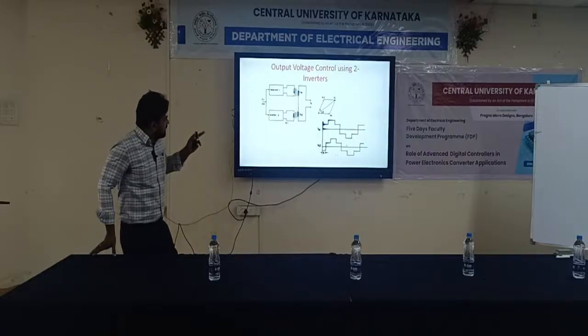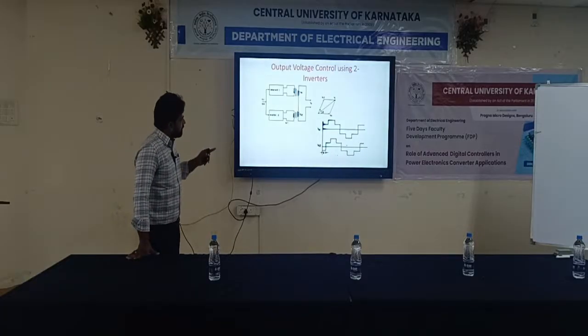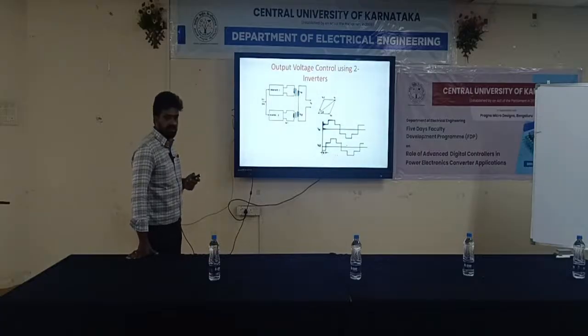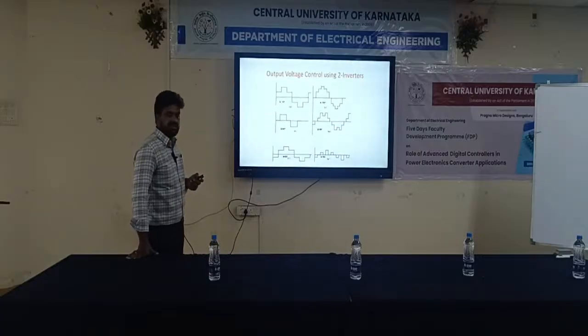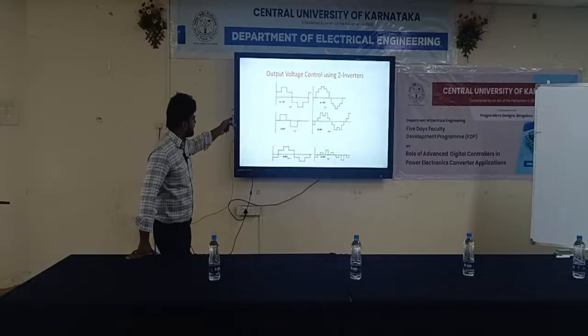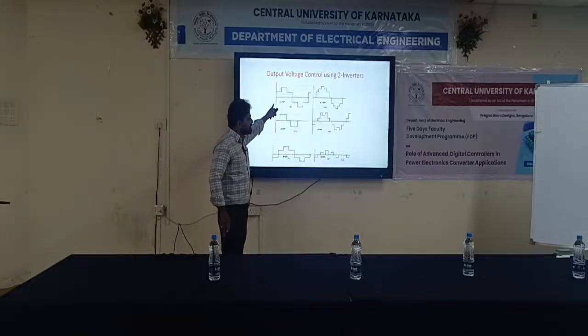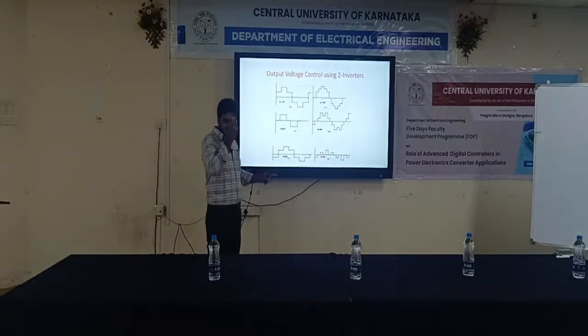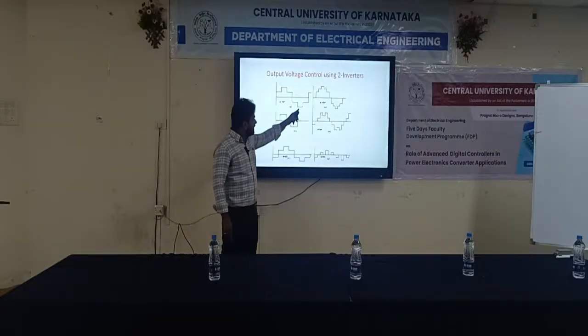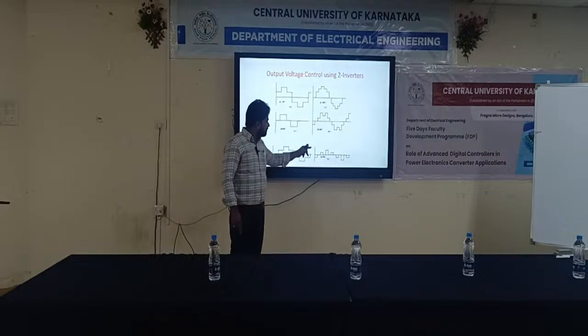The inverter's transformer windings can be given a phase shift such that you get the best total harmonic distortion. With a phase shift of 0, you get the same shape as the inverter voltage. If you go for 30, 60, 90, 120, and 150 degrees, you get different shapes.